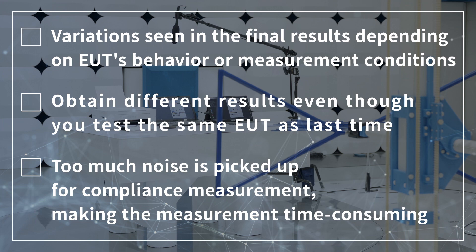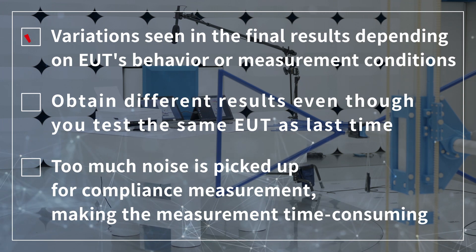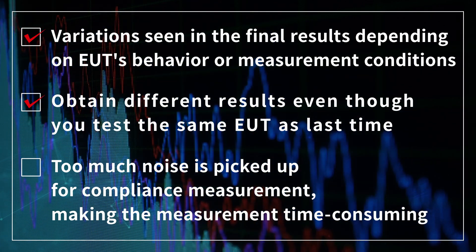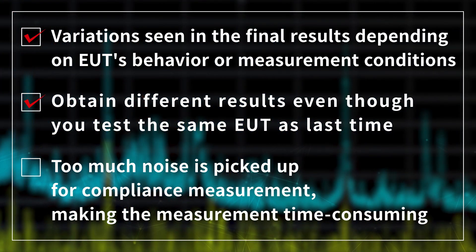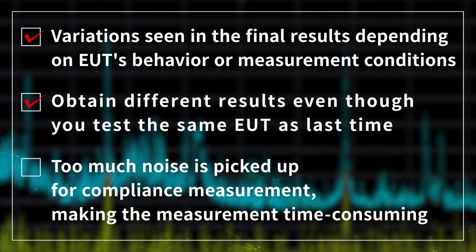Like, depending on the EUT's behavior or measurement conditions, variations can be seen in the final measurement results. You obtain different results even though you are testing the same EUT. Too much noise is picked up for compliance measurement, making it time-consuming to complete the measurements.